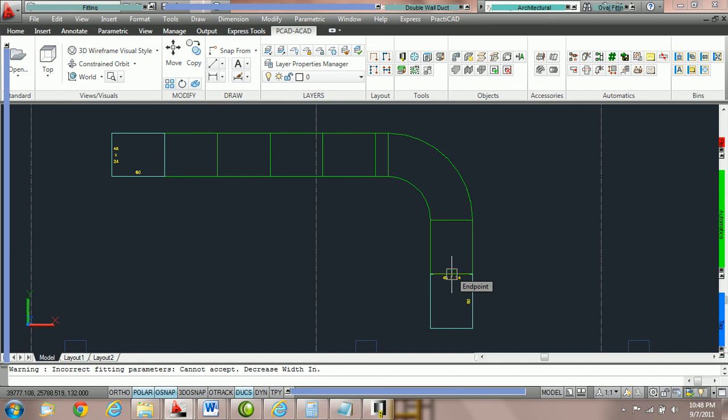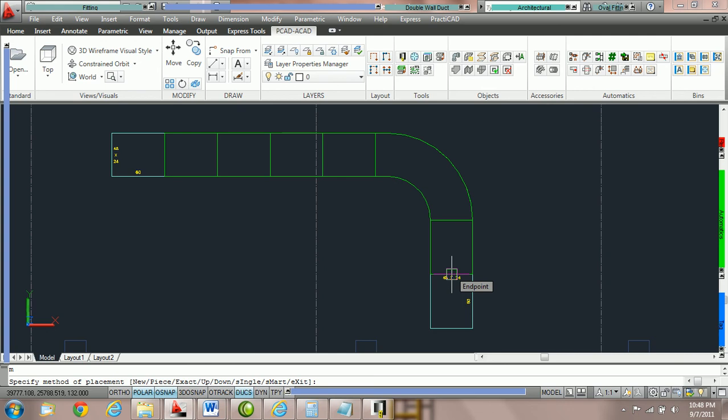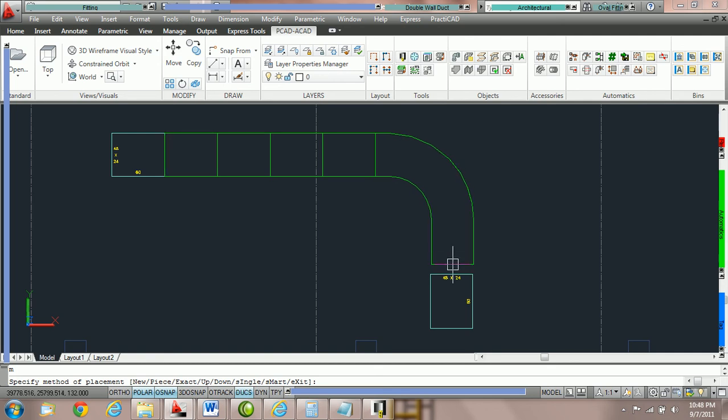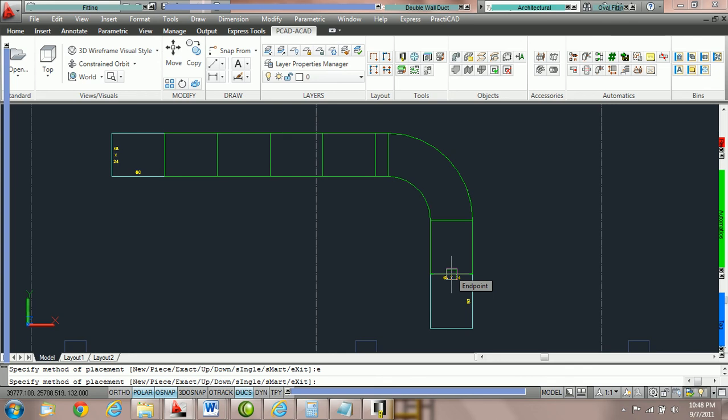Now let's switch it to the smart method. We're going to put in the letter M for smart and then hit the spacebar. That should switch it to the smart method and extend the straights of the fitting so that we no longer have a little piece of duct. Sometimes take note you need to move your mouse just a little bit for it to reset the view. So hit E spacebar for exact, M spacebar for smart.